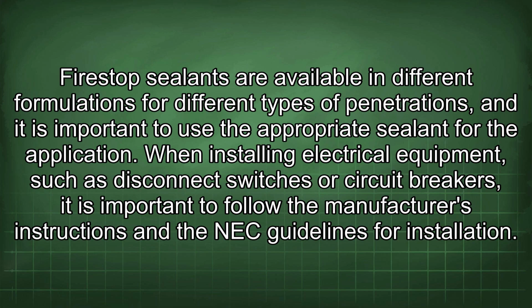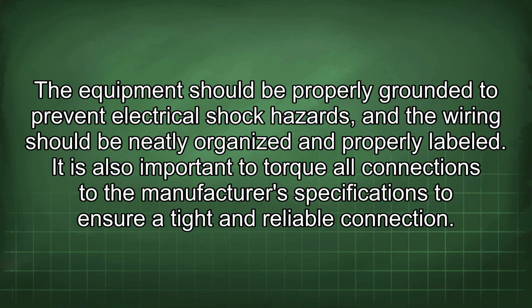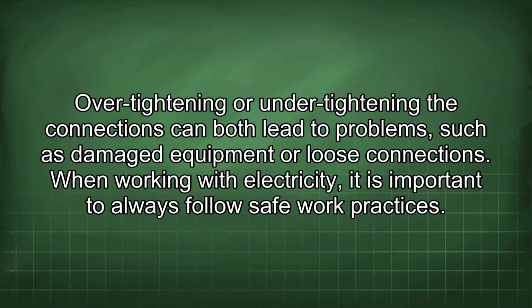sealant for the application. When installing electrical equipment, such as disconnect switches or circuit breakers, it is important to follow the manufacturer's instructions and the NEC guidelines for installation. The equipment should be properly grounded to prevent electrical shock hazards, and the wiring should be neatly organized and properly labeled. It is also important to torque all connections to the manufacturer's specifications to ensure a tight and reliable connection. Over-tightening or under-tightening the connections can both lead to problems such as damaged equipment or loose connections.